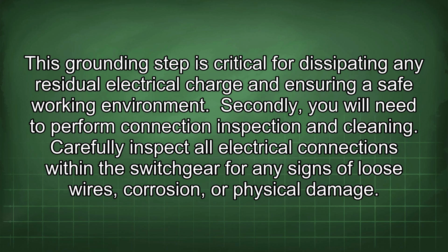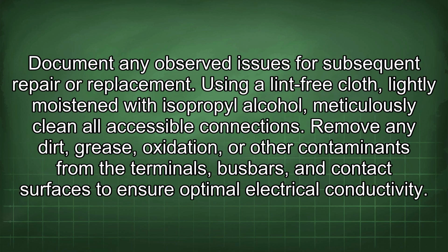Secondly, you will need to perform connection inspection and cleaning. Carefully inspect all electrical connections within the switchgear for any signs of loose wires, corrosion, or physical damage. Document any observed issues for subsequent repair or replacement. Using a lint-free cloth, lightly moistened with isopropyl alcohol, meticulously clean all accessible connections. Remove any dirt, grease, oxidation, or other contaminants from the terminals, busbars, and contact surfaces to ensure optimal electrical conductivity.